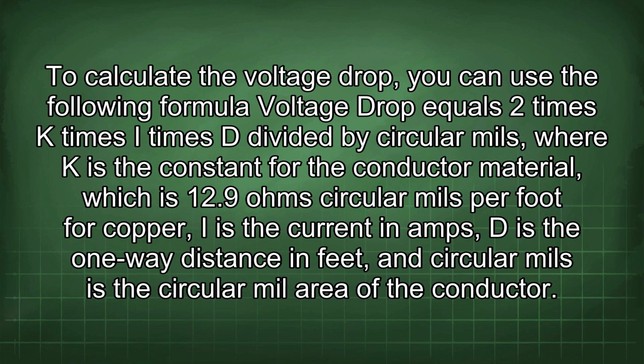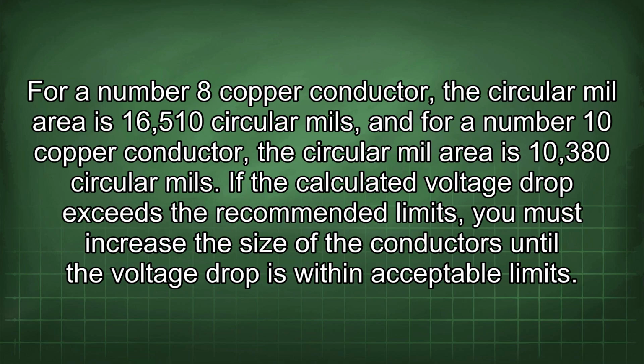I is the current in amps, D is the one-way distance in feet, and circular mils is the circular mil area of the conductor. For a number 8 copper conductor, the circular mil area is 16,510 circular mils, and for a number 10 copper conductor, the circular mil area is 10,380 circular mils. If the calculated voltage drop exceeds the recommended limits, you must increase the size of the conductors until the voltage drop is within acceptable limits.